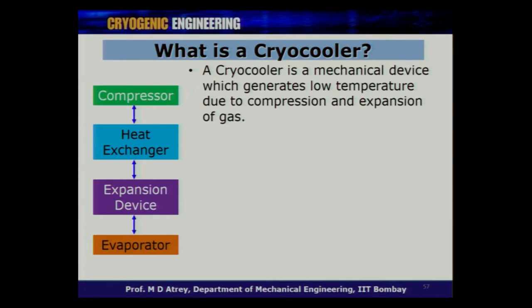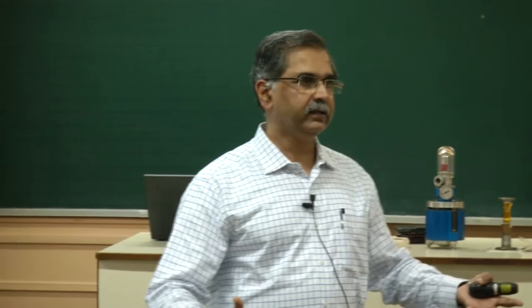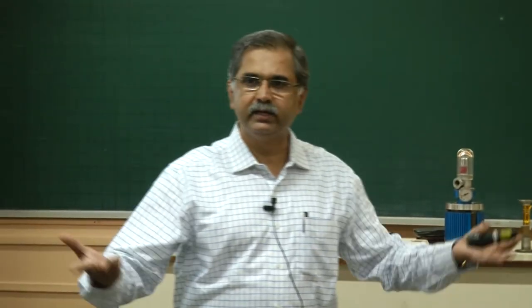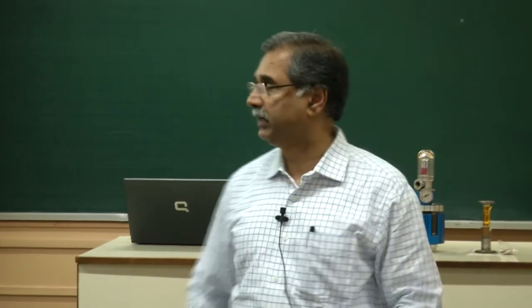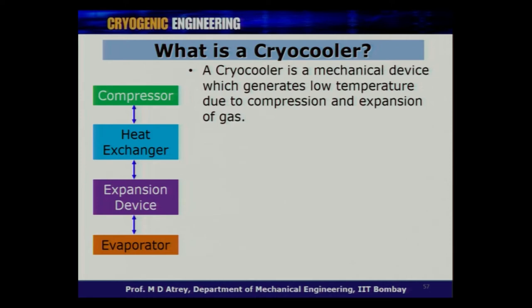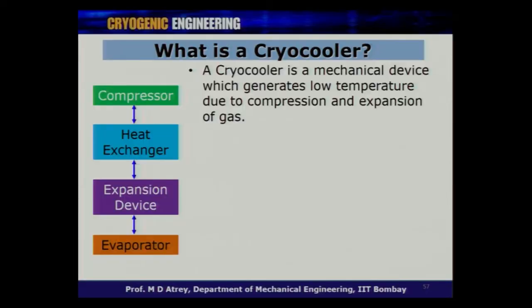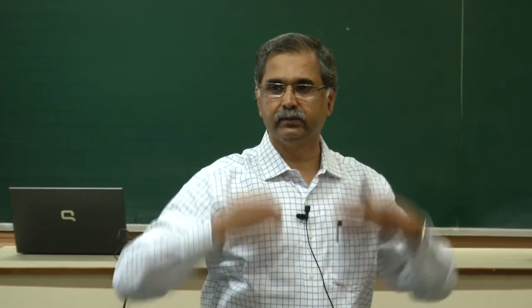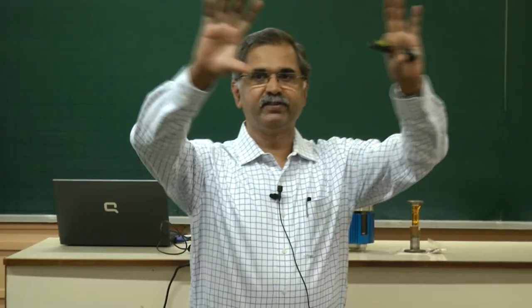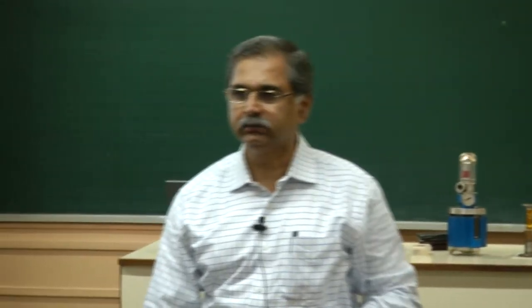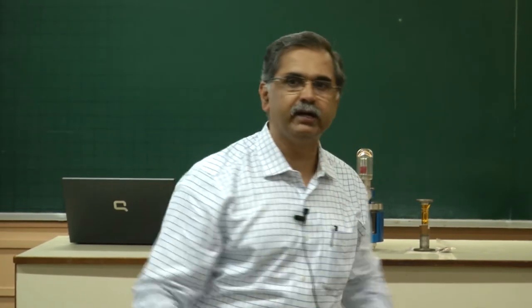Take the example of a domestic refrigerator. It has a compressor. Then there is a heat exchanger — the condenser at the back of the fridge, where the heat of compression is removed. Then there is an expansion device — a capillary tube, which you can see inside the freezer. You get lower temperature, and the evaporator is effectively the entire freezer. Air gets cooled and circulated, so the bottom is warmer and the freezer is the lowest temperature, with natural convection moving air around.